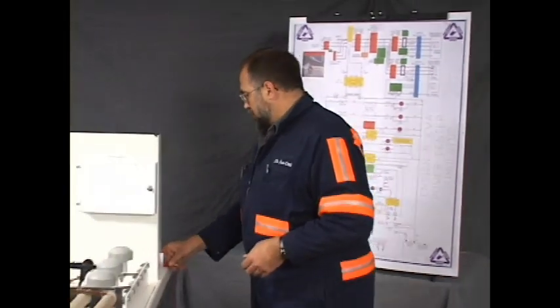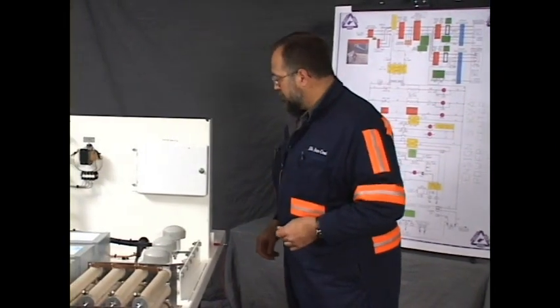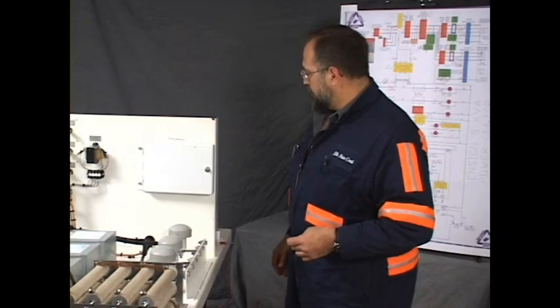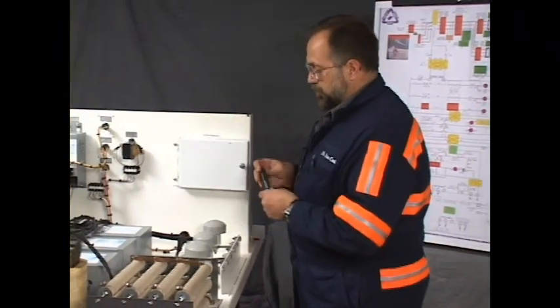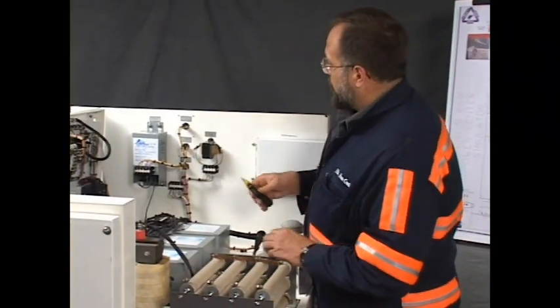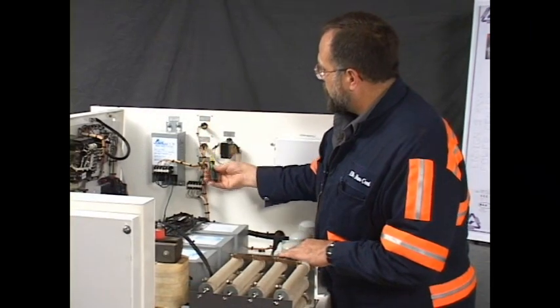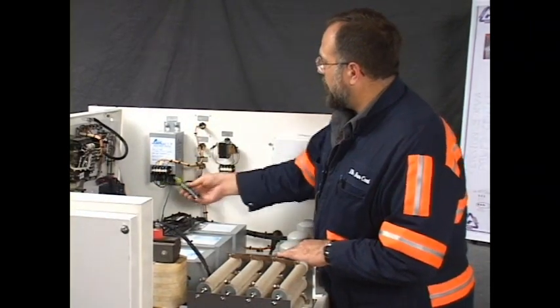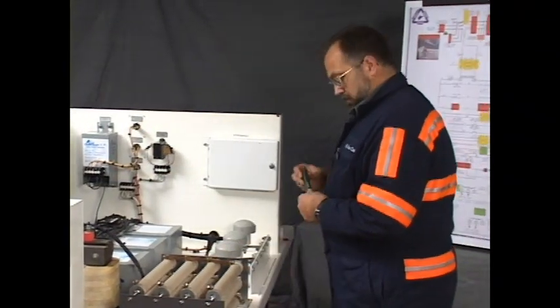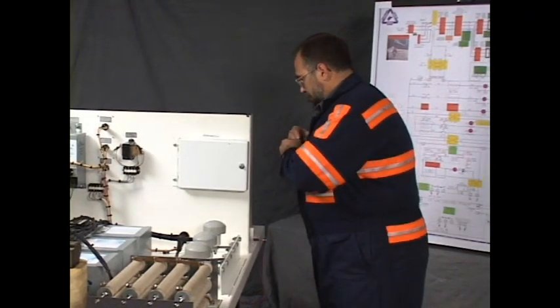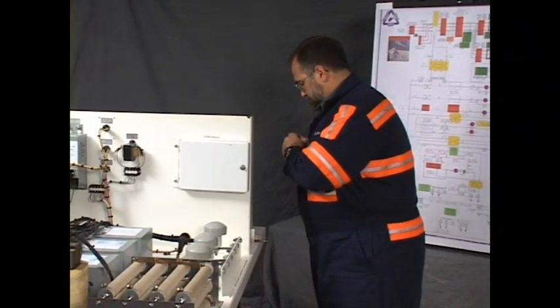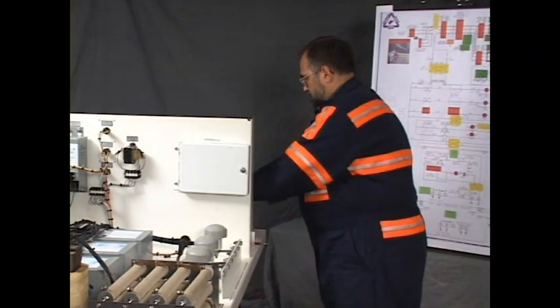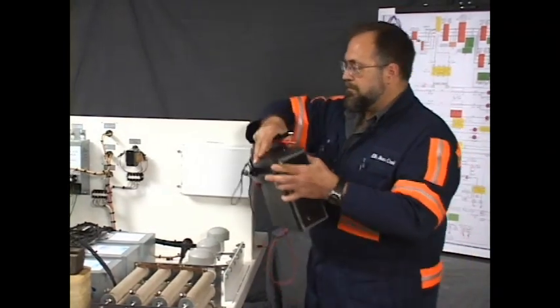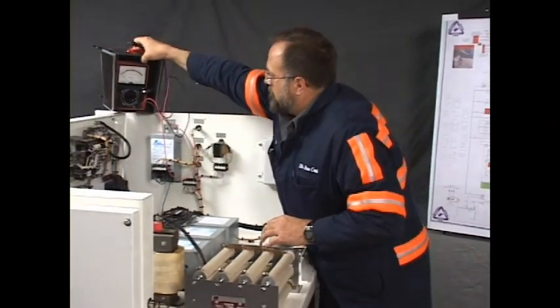So we're locked and tagged. We have a visible disconnect, lock and tag. Just as a precaution here, I'm going to take a voltage reading to make sure that we have no power, and none is indicated. I'm going to take our meter and set it up here in a comfortable spot. You can see it good.